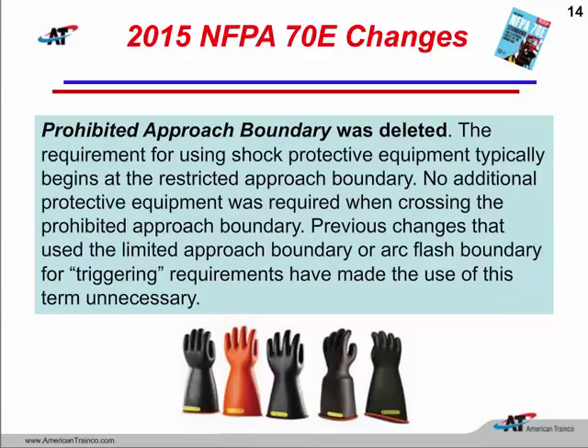So that limited approach boundary was a nice trigger for us. It kept the unqualified people away, and they could not get any closer unless escorted by a qualified person. So that was good. The restricted approach boundary triggered all of our PPE was on. We had 1,000-volt rated tools in our hand, and that we had the proper category of meter in our hand. So that triggered something also. The prohibited approach boundary, in the eyes of the technical committee, did not trigger anything really. So they said there's really no need for that boundary anymore, so it was deleted from our tables. Also deleted from the Article 100, the definitions. So no longer any prohibited approach boundary.